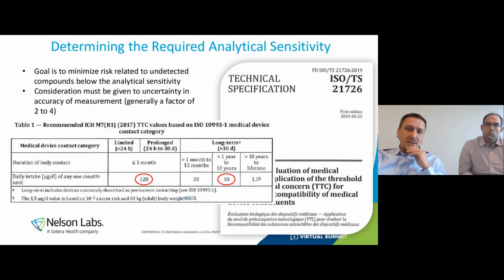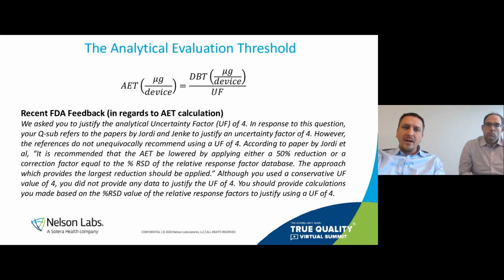So this is a screenshot of the new ISO 21726. It outlines the threshold of toxicological concern for medical devices. You can see for limited and prolonged devices, this threshold is 120 micrograms per day. That means that when you do a chemistry analysis for one of those types of devices, you need to be sure that you're not missing chemicals that might be above that level. So you want to have some sort of evidence that supports that there couldn't be a chemical above 120 micrograms per day that you're not reporting. And that's really what it's all about.